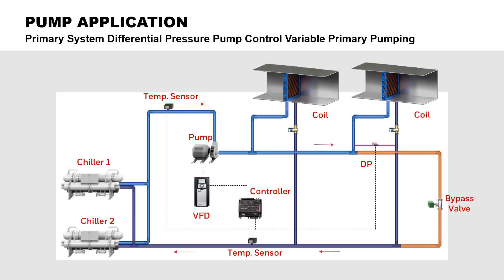Pumps in a variable primary pumping system use a VFD to modulate based on space cooling or heating demands. In this system, there are no secondary pumps to maintain minimum flow to the chiller or boiler. The control contractor will install a water flow meter that monitors flow to the chiller or boiler. On days with low heating or cooling load in the space, the flow meter is used to prevent the pump VFD from further decreasing speed.